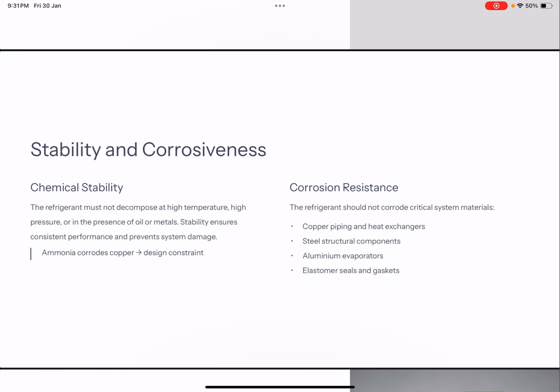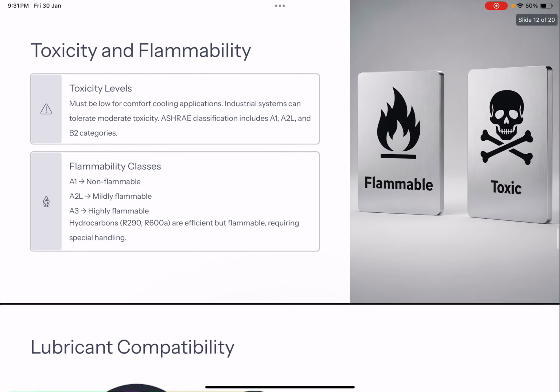Second thing is the refrigerant should not corrode the other critical elements like steel structural components or the aluminum evaporators or the seals and the gaskets, because if they are damaged, that would create leakages and it would impact the performance of the system. So both the chemical stability, that is, the refrigerant should not decompose at high temperature, high pressure or in the presence of oil or metals, as well as the corrosion resistance are equally important in the choice of refrigerants.